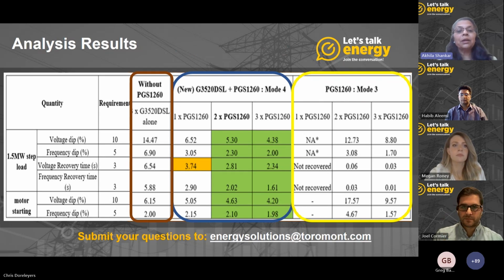This slide is pretty busy and it will require some explanation. So what you're seeing here in the first column are the loads that were applied, the 1.5 megawatt in the first step and the motor starting in the second step. The second column shows you the various parameters that were recorded for the analysis. The third column talks about the acceptable limits for these parameters that were measured. For instance, this requirement was that the voltage dip should not exceed 10%.